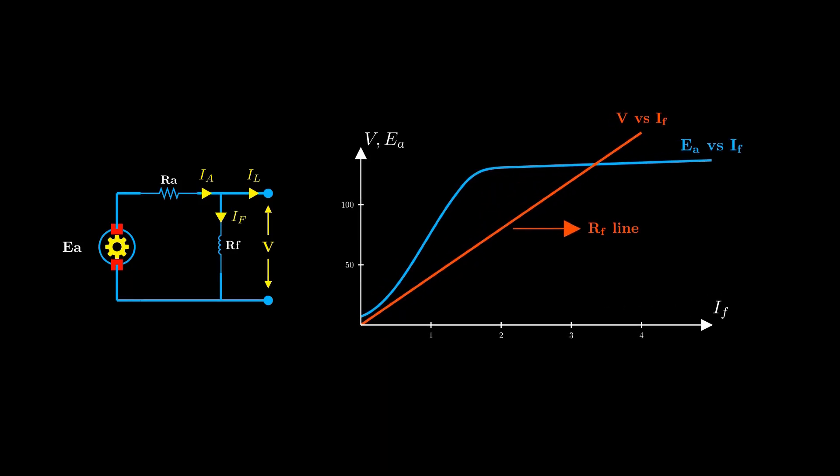More flux means more induced EMF, more EMF means more field current, and more field current creates even more flux. This rapid, self-reinforcing process is called voltage buildup.